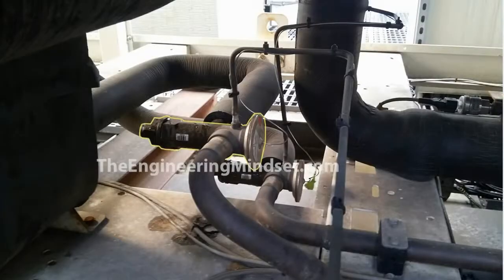The next expansion valve we're going to look at is the thermal expansion valve. In the real world, the thermal expansion valve looks just like this. This one is actually on an air-cooled chiller, but it's still got the flow of refrigerant coming through and then going off into the evaporator, and you've also got the equalizer valve coming through there, and attached to the top of the thermal valve is the capillary tube, which goes off and measures the superheat.